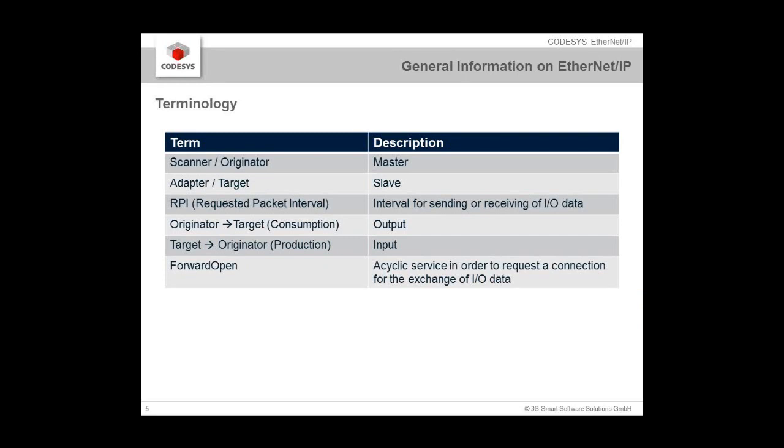Some terms on EtherNet/IP. In CODESYS we often speak about master, but in the EtherNet/IP world this is the scanner or the originator, whereas the slaves are the adapters or the target. Then there is the requested packet interval, which is the interval for sending or receiving I/O data. When we're talking about outputs, this is called originator to target, and the other way around, target to originator is the input. Then there is an acyclic service called forward open, which is necessary for every new connection so that the data exchange can be started.